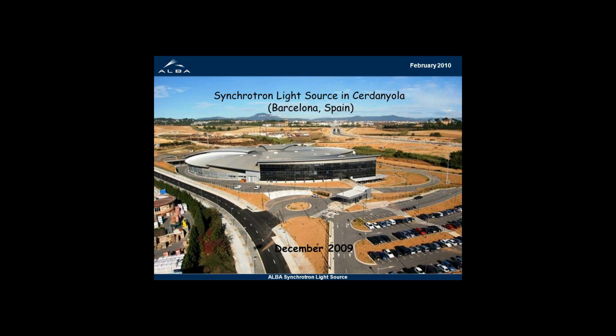At incident beam energies which are much higher than the absorption edge, photoelectron scattering causes ringing modulations called the extended X-ray absorption fine structure, EXAFS. Fourier transformation of the EXAFS regime yields the bond lengths and number of the atoms surrounding the absorbing atom. It is therefore useful for studying liquids and amorphous materials as well as sparse species such as impurities. A related technique, X-ray magnetic circular dichroism, XMCD, uses circularly polarized X-rays to measure the magnetic properties of an element.